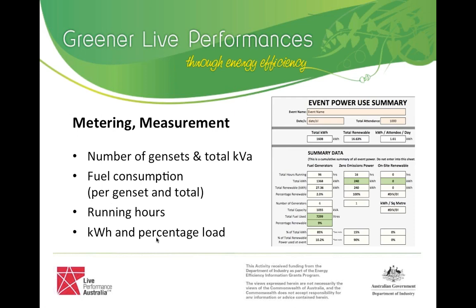Things that should be measured include the number of generators and total KVA on site, which is important to log and reflect on from event to event. Fuel consumption per generator and in total should definitely be measured. Running hours are really important because that puts the whole thing in context — there's no use saying you had a certain number of generators and used that much fuel without also tracking how long they were turned on. The true measure of efficiency is optimising the power load at 70 to 80 percent sweet spot for as much time as possible.